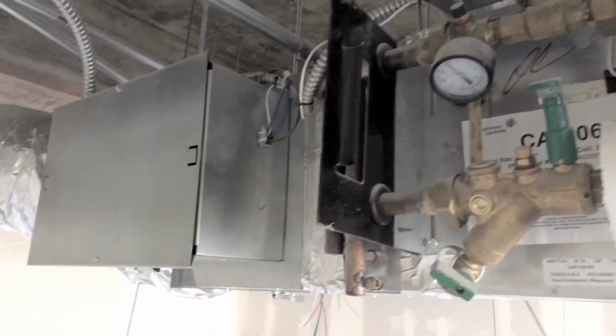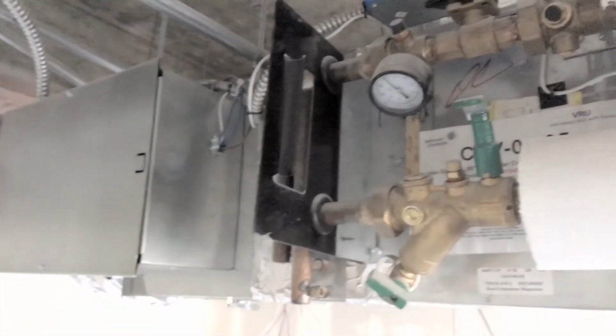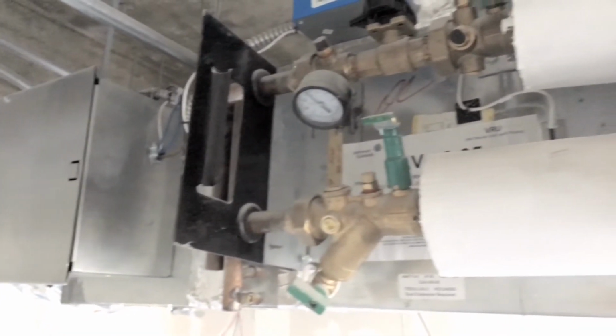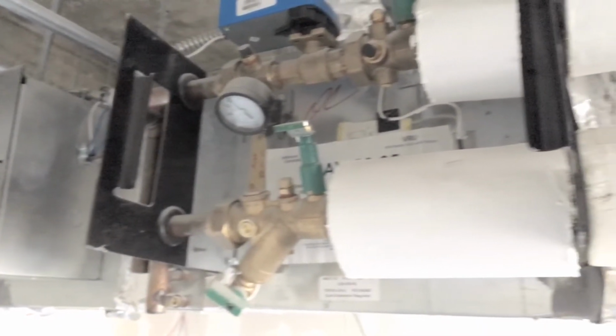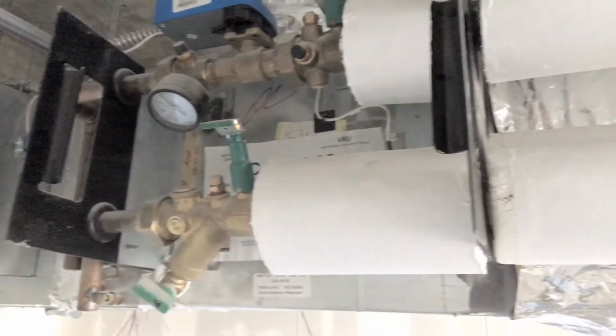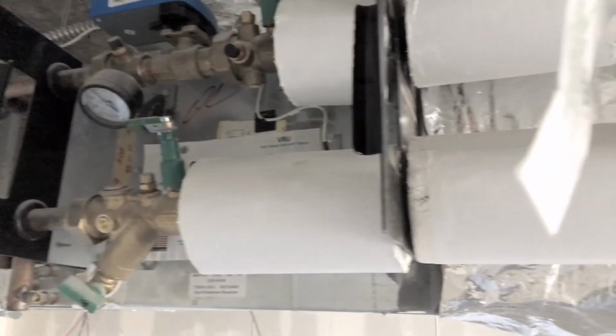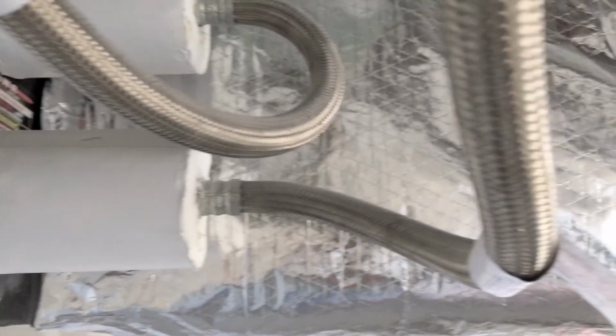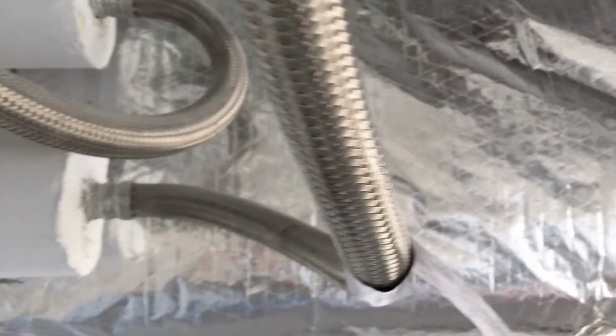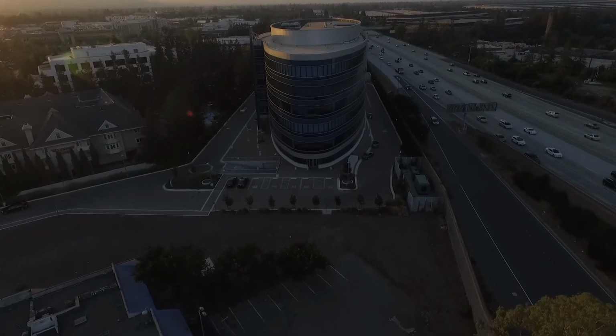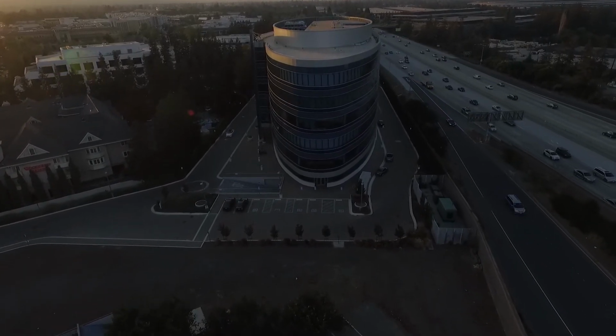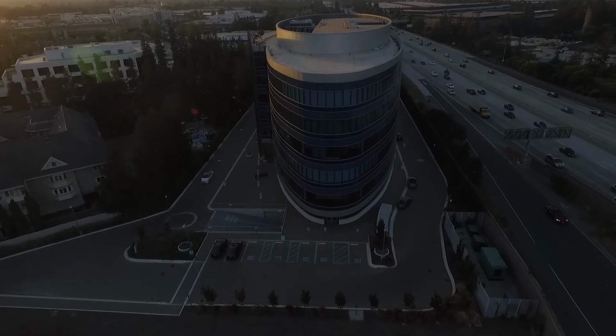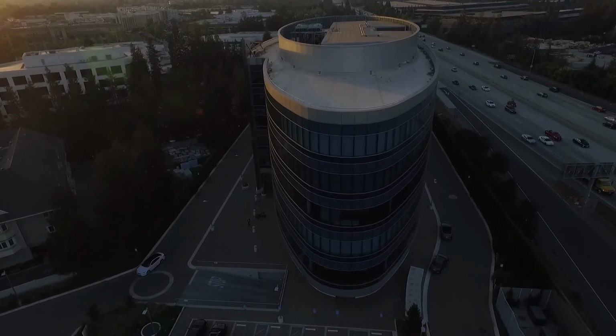A hydronic heating coil usually has 1 or 2 rows of copper or aluminum coils that the heat transfer fluid is pumped through, and the air from the air handler is blown across. This allows you to turn on or off the heated HTF that is being pumped through the coils, in turn letting you adjust the temperature of the air being blown out of the vent in the room or that specific zone. I hope that this presentation has helped you better understand how many of the heating and cooling systems we operate or are surrounded by every day keep you comfortable.